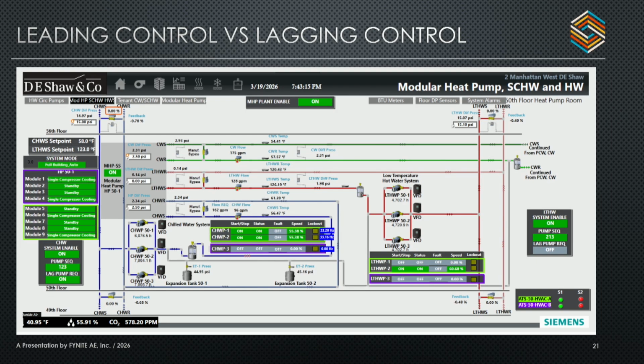So this is a screen capture of the actual system in operation. What you can see on this is the flow rates shown here: 96 GPM on the chilled water, 128 on the hot water, and 175 on the net water, which is going to the bore field or the cooling tower or whatever source you're going to be using. And that represents a lot of overpumping that's happening.